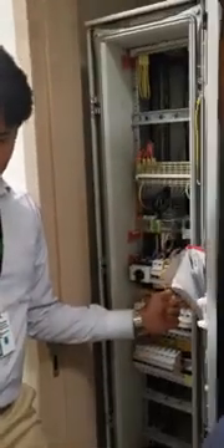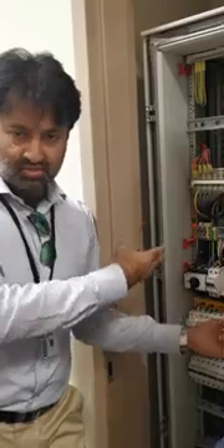Second thing you check is the transformer overload. The way to check that is we have to change the current setting in this device with the menu option. There is a built-in menu, and we change the alarm current setting in that. Right now it is 22 ampere according to the transformer capacity. We change it to 5 ampere, and you connect any load higher than 5 ampere in the outlet. And then you ultimately see the transformer overload alarm popping up.